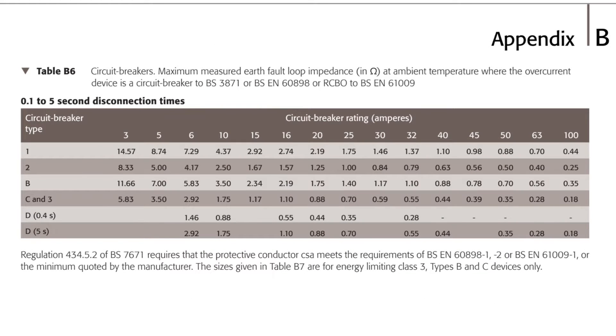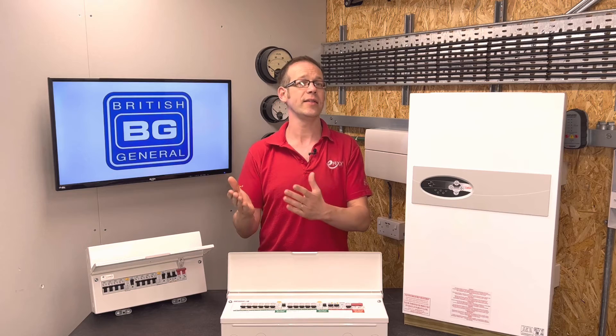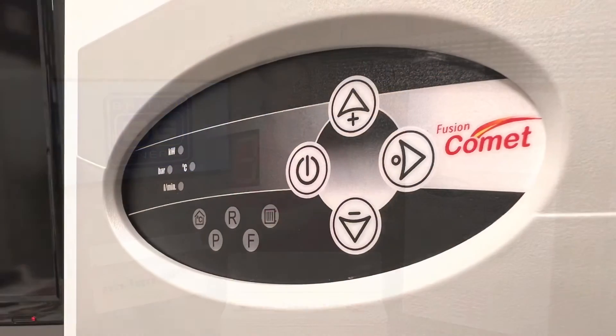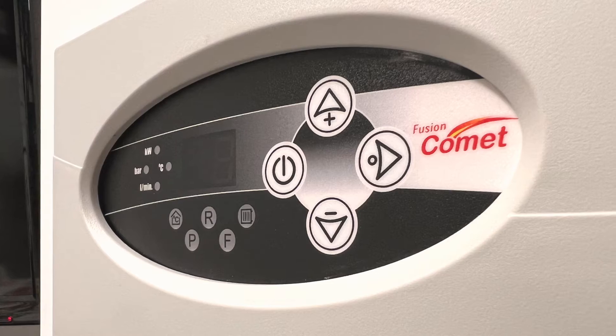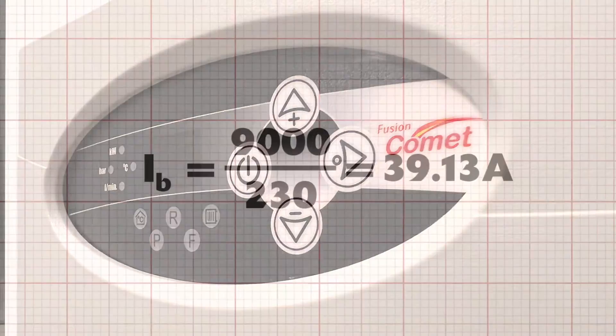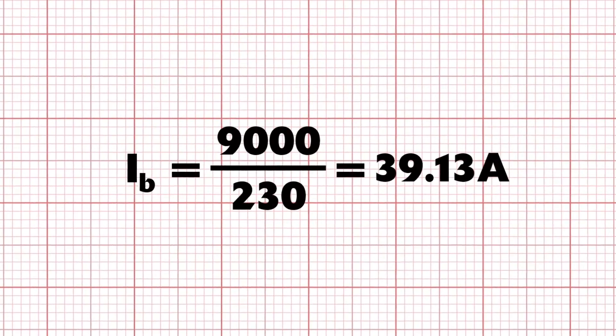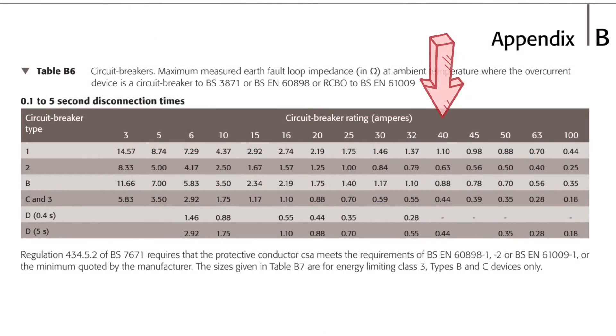A quick word of warning: not all manufacturers make all the sizes listed in those tables. For example, table B6 in the on-site guide lists MCBs across the top — while this table is designed for maximum earth fault loop impedances rather than as a circuit breaker size guide, it is a very helpful reference. In a previous video in this series we started designing a circuit supplying a Fusion Comet electric boiler, and calculated it would draw 39.13 amps. The next size up from that design current is a 40 amp breaker, making it our natural choice.